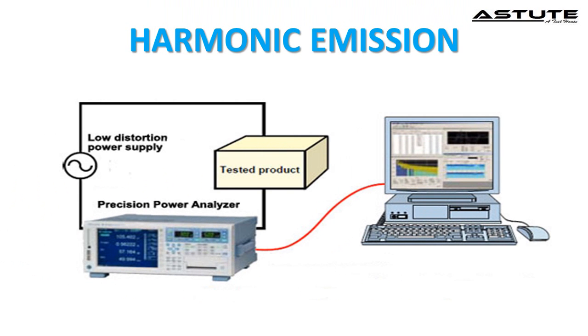The increasing use of electronic equipment fitted with switch mode power supplies has led to an increase in distortion of the public power supply. Such loads draw non-sinusoidal current, which contains harmonic frequencies at multiples of the 50 Hz and 60 Hz supply frequencies. This can lead to significant currents flowing in the neutral conductor, resulting in cable and transformer overheating. This is also known as phantom power because it has to be transported through cables and transformers, but is not useful. So, for checking the level of harmonic emission of equipment, the harmonic emission test is conducted.